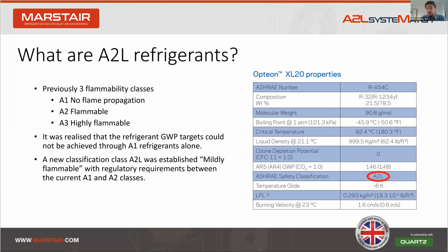So what are A2L refrigerants? Well, to help meet the F-gas phase down, we needed something new. So a new category of refrigerant was developed, the A2Ls. This allows slightly less stringent refrigerant charge restrictions within the regulations. So more refrigerant is allowed than, say, flammable refrigerants such as hydrocarbons. The example shown here is R-454C.